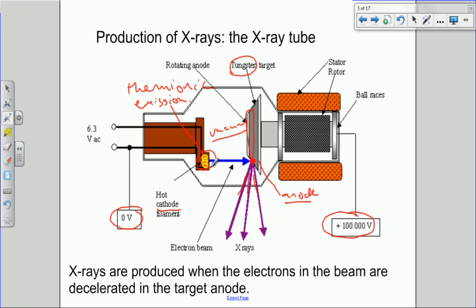In summary then, we've got thermionic emission, electrons being evaporated or emitted from the surface of this wire, and accelerated across this evacuated gap by this very large positive potential difference. When they get to the other side, they hit this tungsten target, which is the anode, because it's positive, interact with the atoms in the tungsten, and X-rays are given off. In order to keep it cool, it's rotated at very high speed by this big electric motor at the back. That's the X-ray tube.